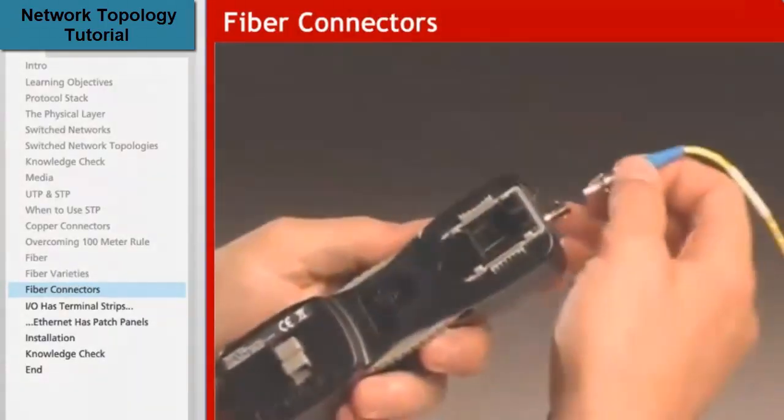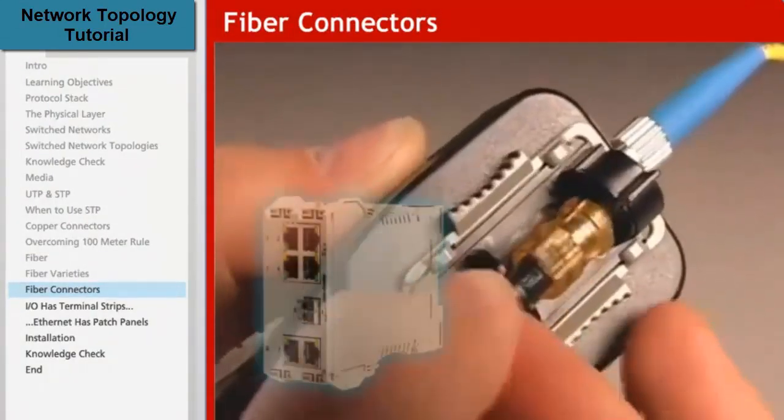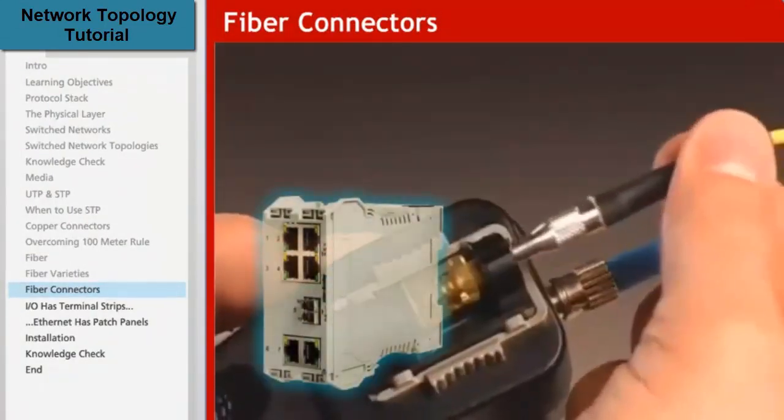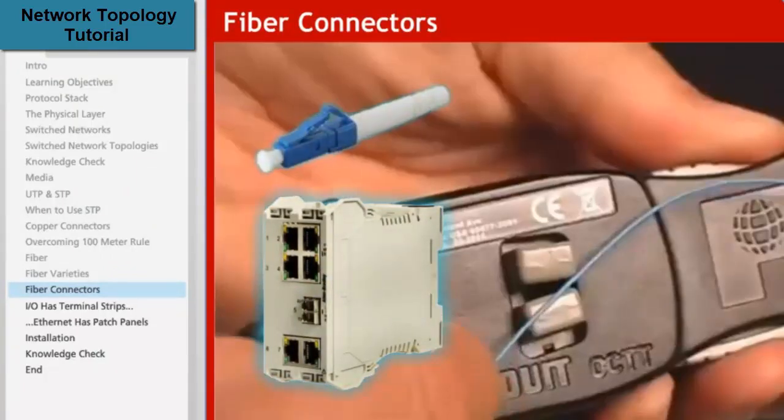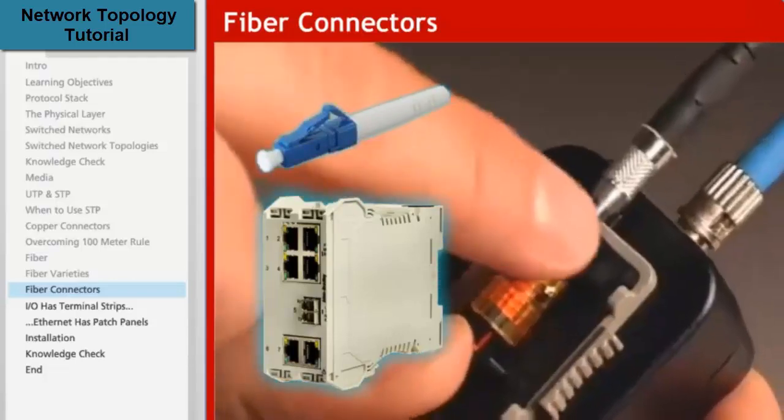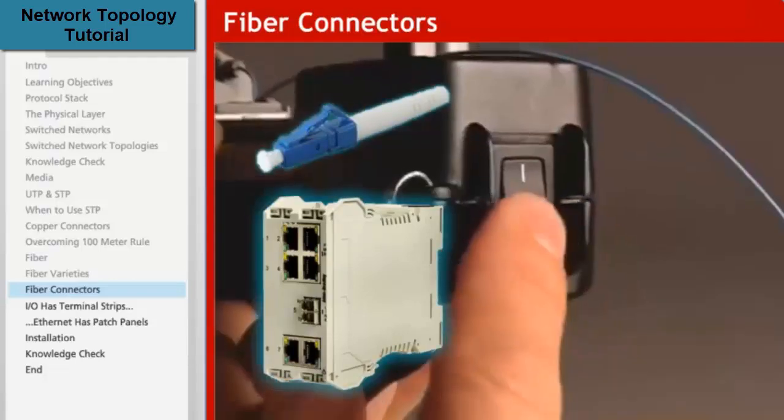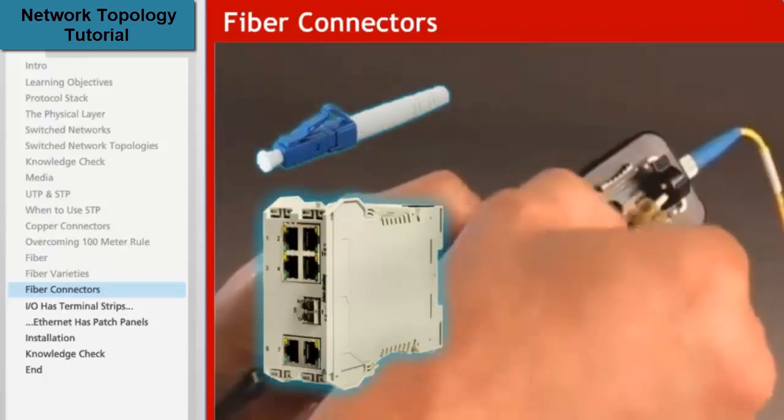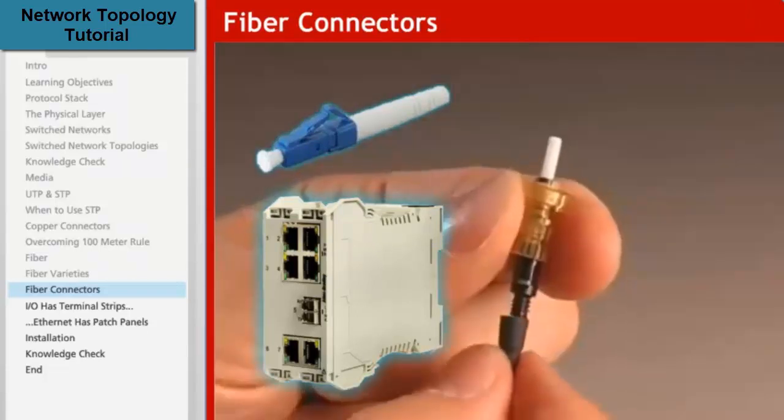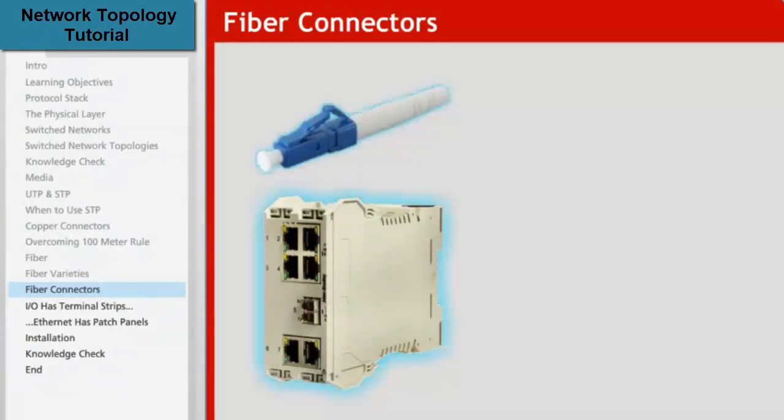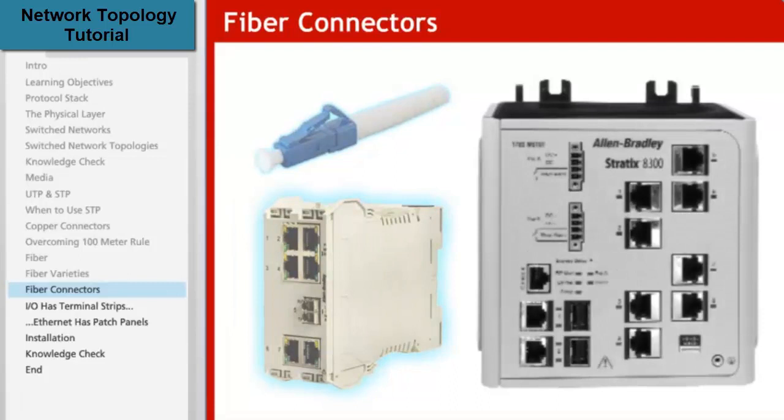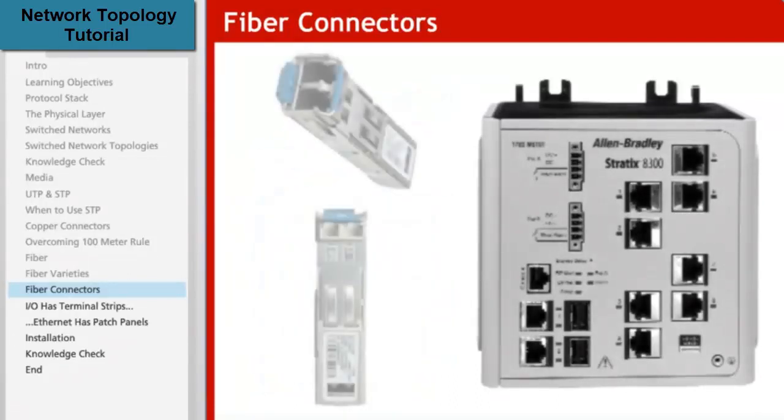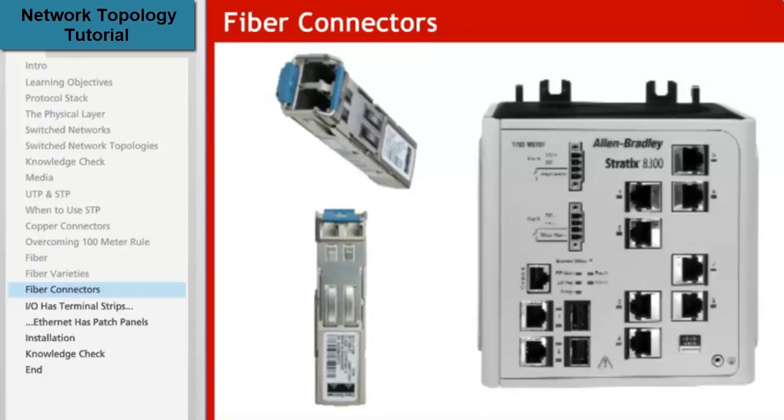Fiber cables must be terminated with one of several different types of connectors. When connecting to a Stratix switch, LC type connectors are used. When using Stratix 2000 switches or the 1783 MX08F fiber expansion module for the Stratix 8000 and 8300, the LC connectors are inserted directly into the fast Ethernet fiber transceivers that are built into the unit. But when using the gigabit ports on the Stratix 8000 or 8300, then an SFP or small form factor pluggable transceiver must be used. The SFP is inserted in one of the slots on the front of the 5700, 8000 and 8300 or on the bottom of the 6000. Then the LC connector is inserted into the SFP. Several different types of SFPs are available depending on the switch in use, the customer's application, and their choice of single mode or multi-mode fiber.